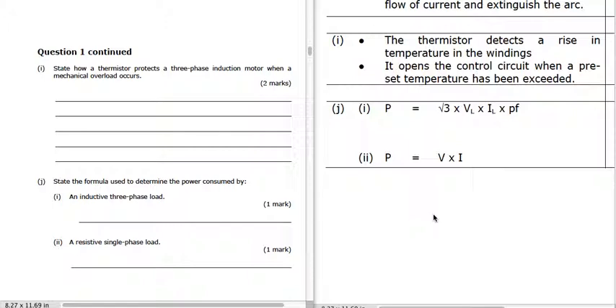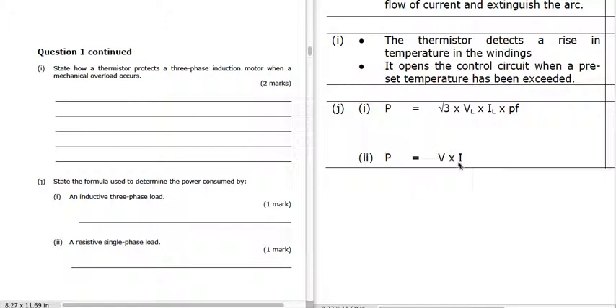A thermistor protects a three-phase induction motor when a mechanical overload occurs by looking at temperature. It detects a rise in temperature in the windings and opens the control circuit when that preset temperature has been exceeded — it knows when there's an over-temperature. For power of an inductive three-phase load, the formula is P = √3 × VL × IL × power factor. For a resistive single-phase load, power equals V times I.